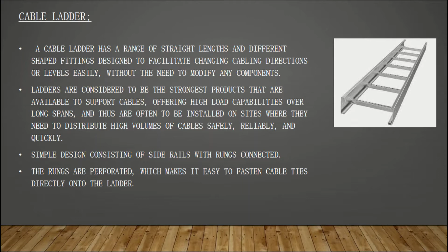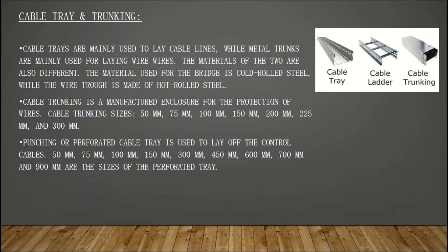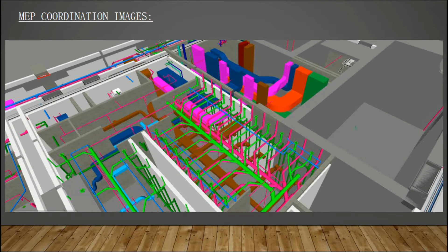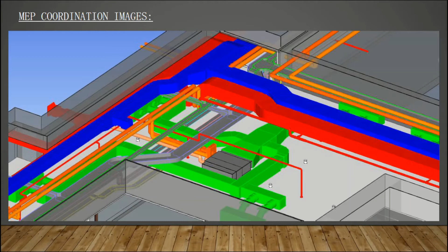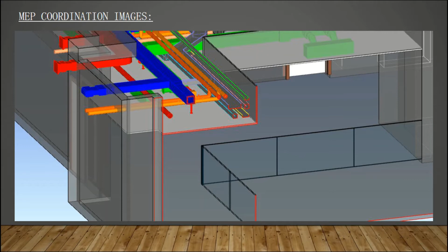The following are some of the basic information that needs discussion before we start the coordination between other services. It follows: total void space between the ceiling and the soffit, false ceiling height from finished floor level, proposed structural beams in their route and its depth, services running in the given route, for example HVAC, firefighting, drainage, gas, water supply, and so on, type of false ceiling and their support type, approved materials, method of installation, manufacturer recommendation for all the services. These are some of the information that needs to be taken into account before we start the coordination.